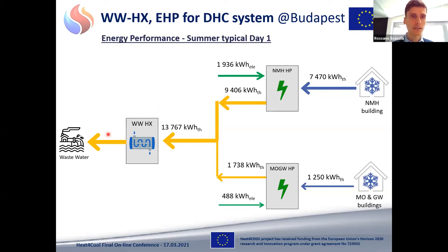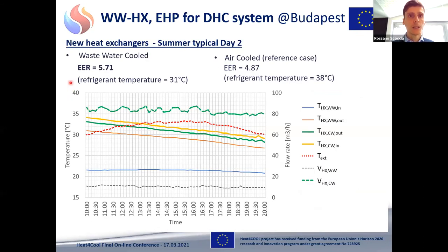This is useful for the next slide, where I show you a focus on the temperatures and the flow rates on the two sides of the heat exchanger for another typical day. First of all, you see a very good EER around 5.7 for this wastewater cool system, which is 20% higher than a reference case, which could be an air cool system with 4.87.